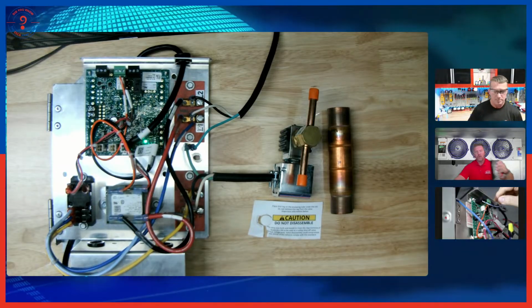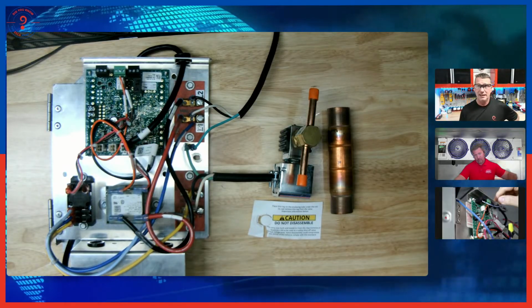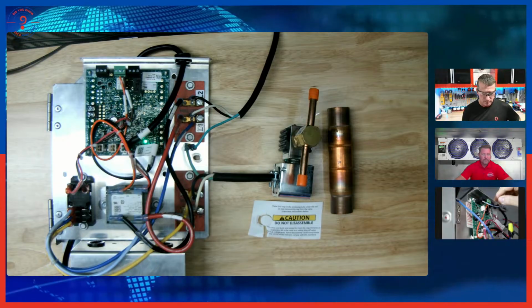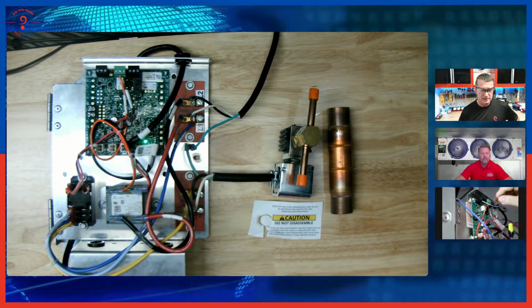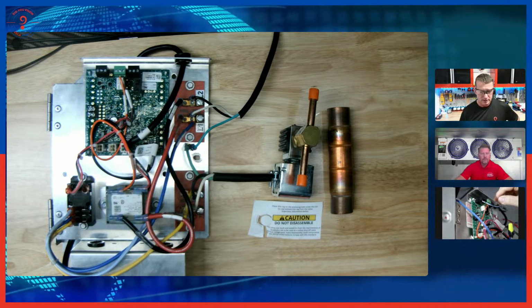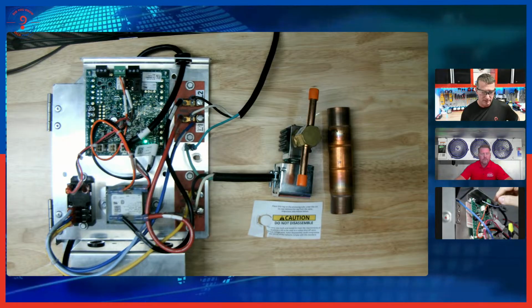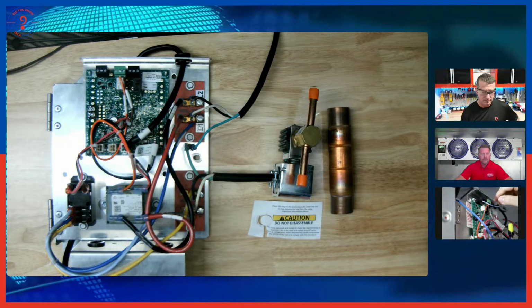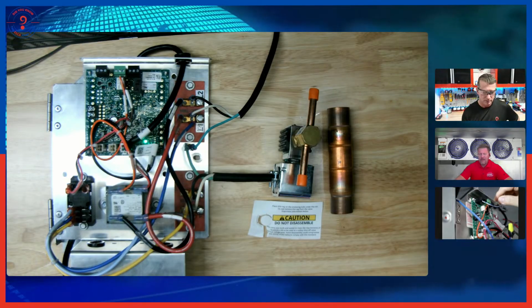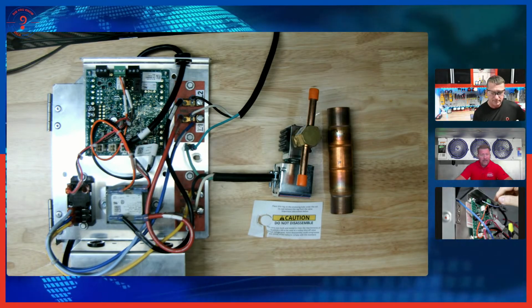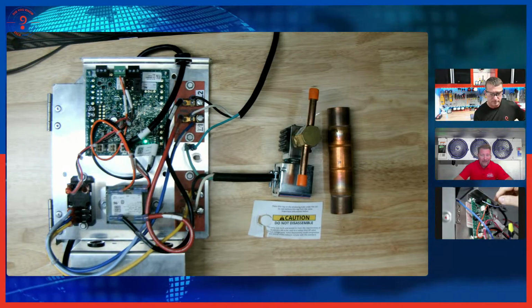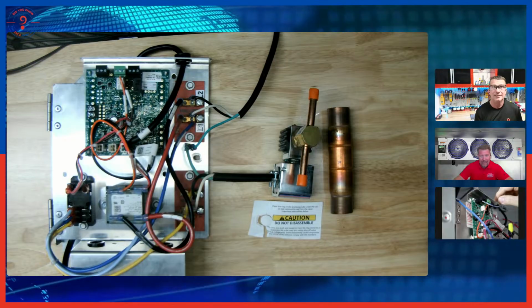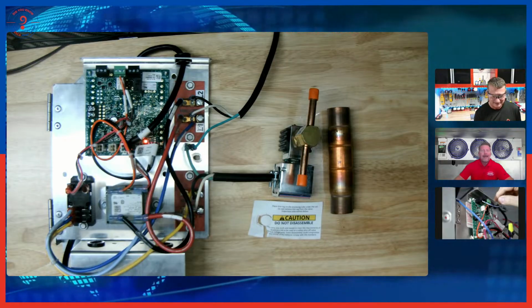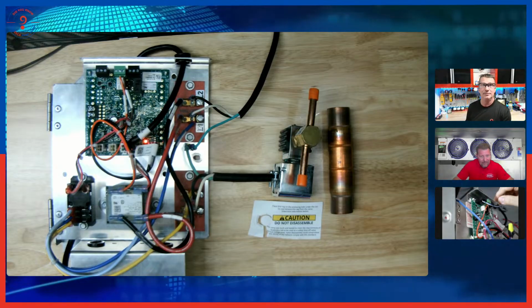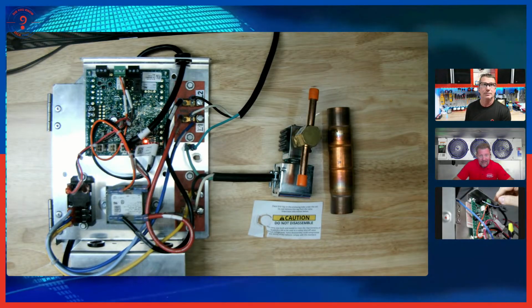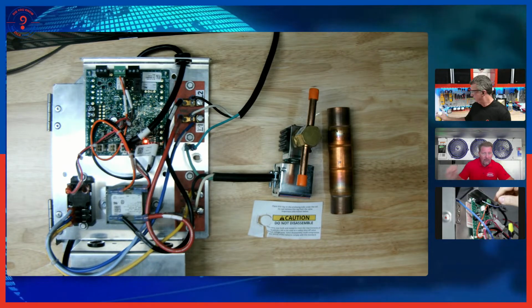So we're in standard operating mode. And so let's go back and try that again. We're going to see if we have a very small refrigerant leak in the space. Not enough to hit the lower flammability limit, but enough to introduce a cautionary action. And I believe Don Fort covered this with you when he was on here, and I watched it, and I forgot to write down the thresholds because Don knows his stuff like the back of his hand. If anybody's ever seen Don on here. Yeah, there we go. Okay, there we are. So as you can see, you've got a yellow and a red flash.